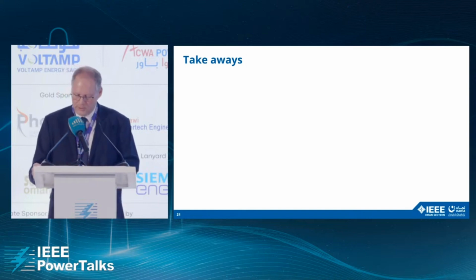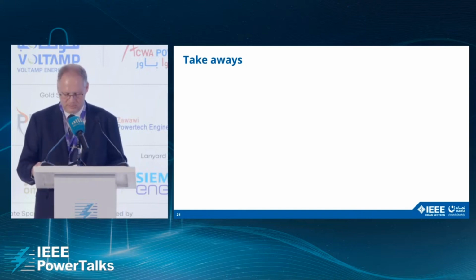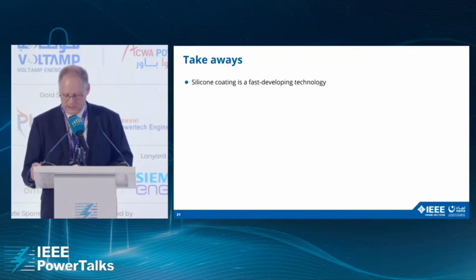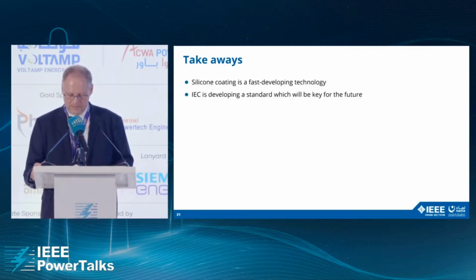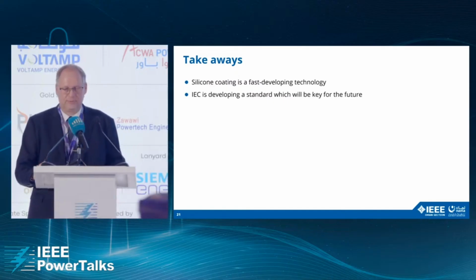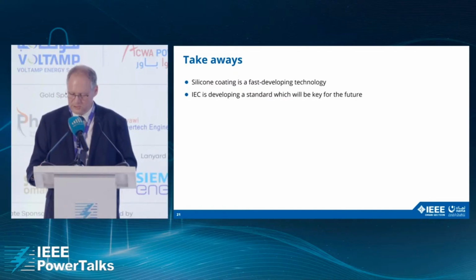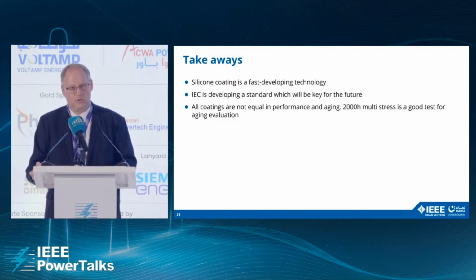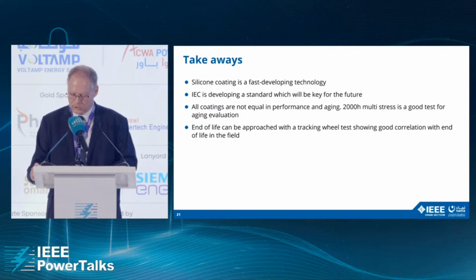To conclude, I would like to remind the following key points to keep in mind. Silicone coating is a fast-developing technology. IEC is developing a standard for RTV coated insulator, which will be the key for the future. All coatings are not equal in performance and aging. A 2,000-hour multi-stress test is a good test for aging evaluation. End of life can be approached with a tracking wheel test showing good correlation with end of life in the field. All coatings do not provide the same longevity.